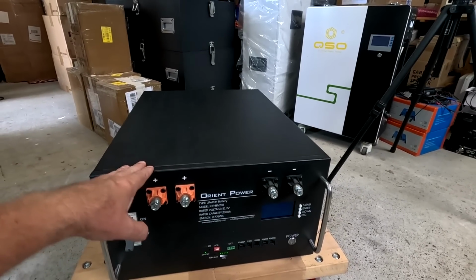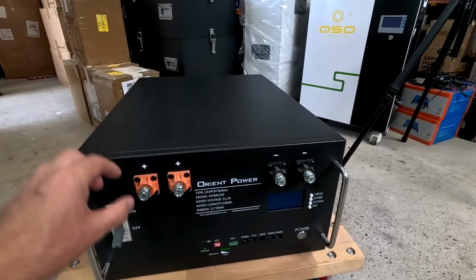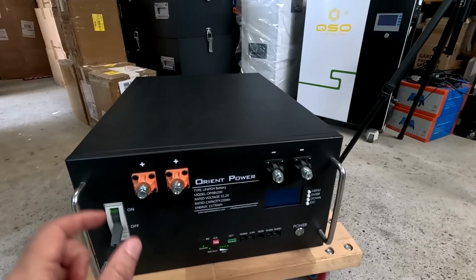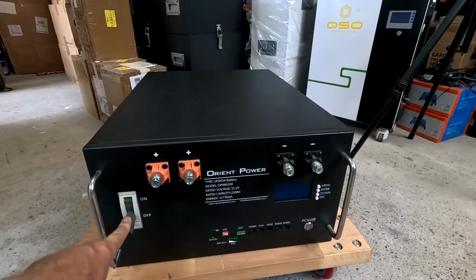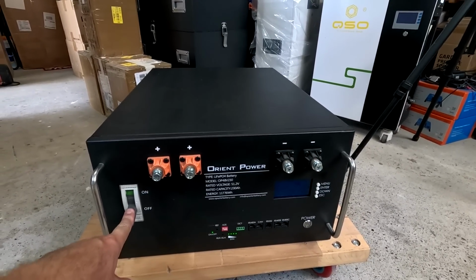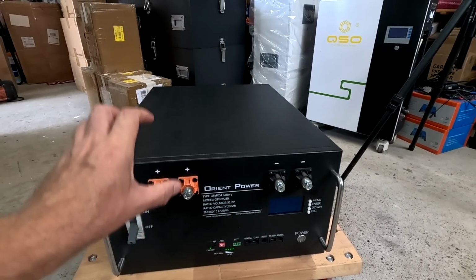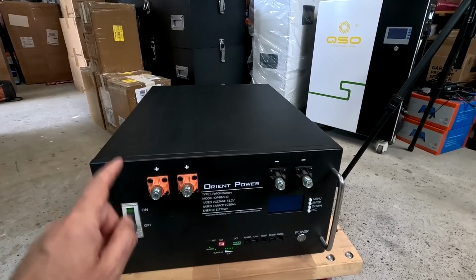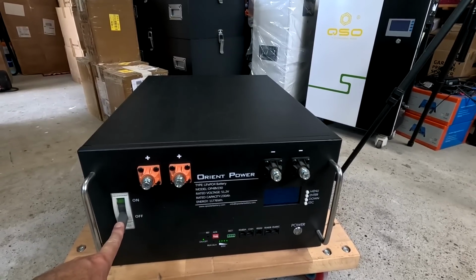So with these pre-assembled batteries, I'm always recommending to get an external fuse or breaker for each of your batteries. Don't rely on the 250 or 200 amp circuit breaker which comes with the battery. You can see the internal cables, as well as the external cables you probably put in, are not rated for these high currents. None of the batteries we have ever tested had the appropriate cables for the circuit breaker installed. So if you want to check on your battery, I link these documents down under this video. This is what I usually use, and it gives you a rough idea of what is going on in your battery, what kind of cables you are using, and what kind of current your cables can withstand.